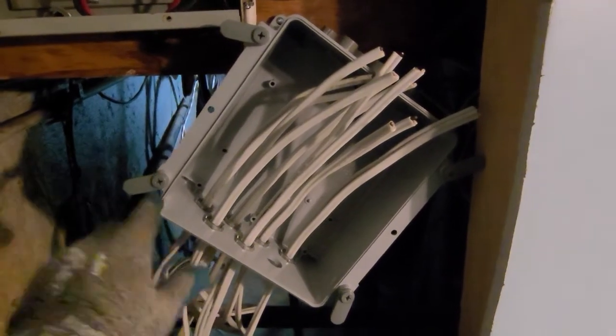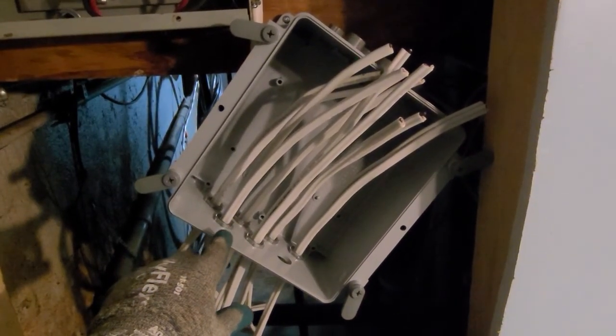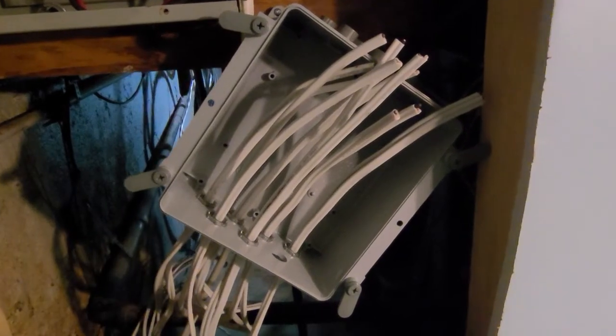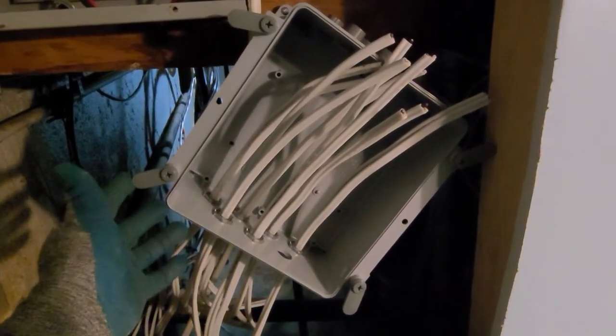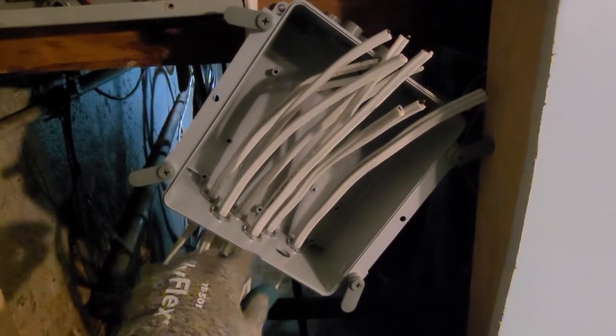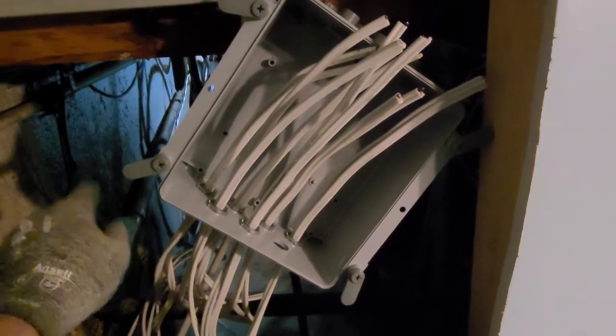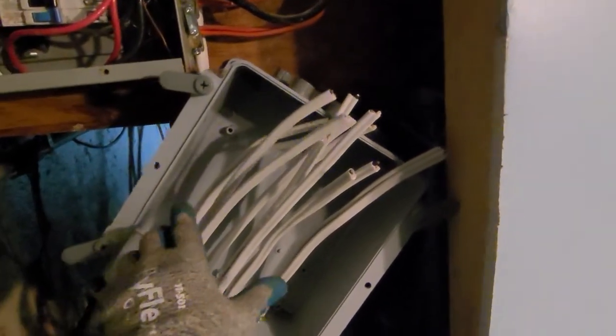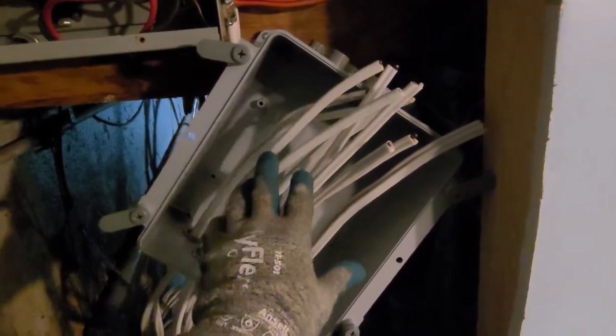Guys, as you can see, this is the junction box for those short cables for the newer panel. So we have to have a junction box so we can splice the shorter cable with the new one, so we reach the newer electrical panel, and the older ones were coming from the top of those connectors into the 8x8 by 4 junction box. Actually, we don't have to use this type of metal wire connector.